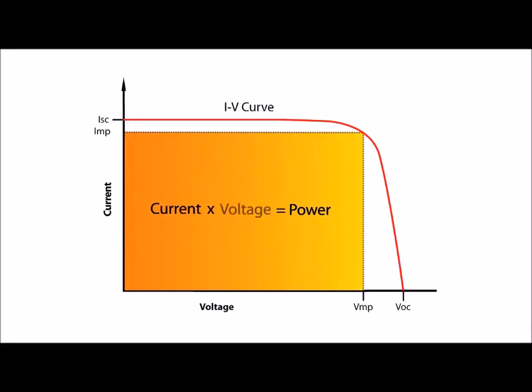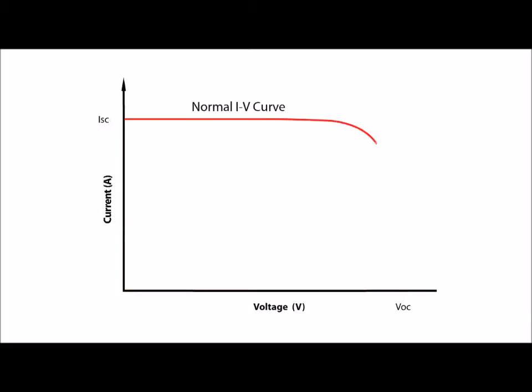Power is the product of current and voltage, thus maximum power is achieved at the knee of the IV curve. A full IV curve trace allows the observation of PV performance at and around the maximum power point. Further diagnostic value is derived from examining the shape of the IV trace.